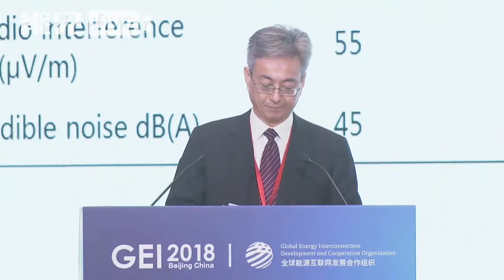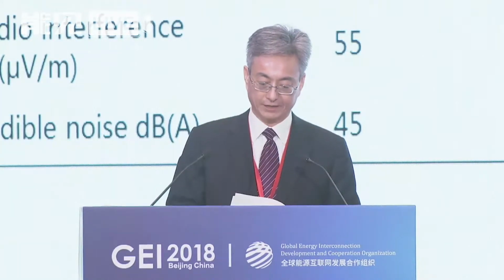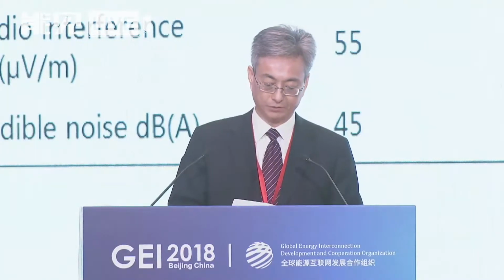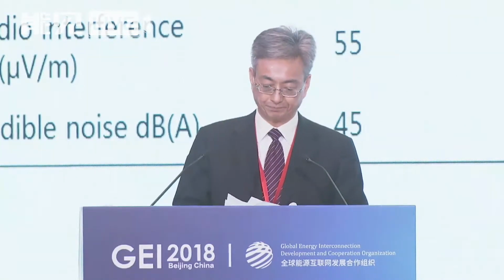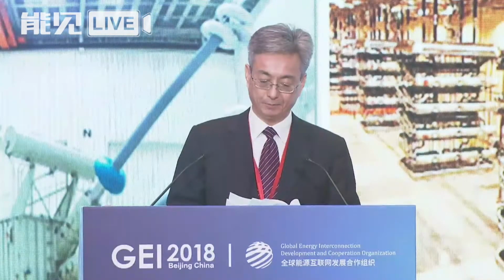The conductors of UHV lines are featured by complex construction and large dimensions, and there are strong electric fields around the conductors and serious electromagnetic interference induced by corona. Based on theory and experiment, the electromagnetic field distribution pattern of the complex multi-conductor system of UHV lines is analyzed, and a complete set of prediction algorithms is developed and proven in practice. With the application of large section conductor bundles, the electromagnetic environment of the UHV system is controlled to the kV level, and the actual measurements are much lower than the limits specified.